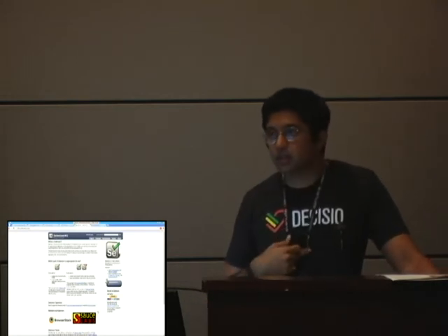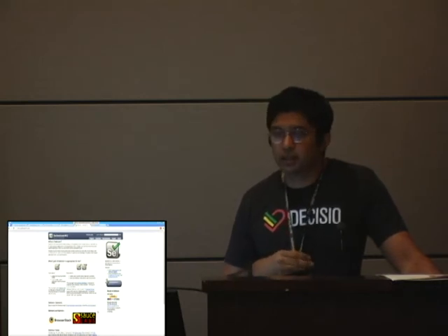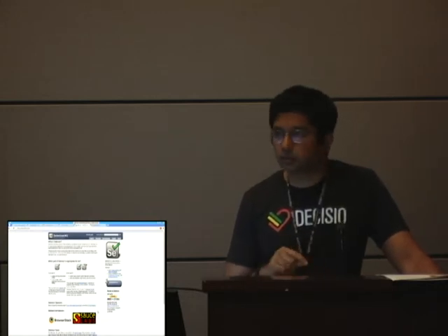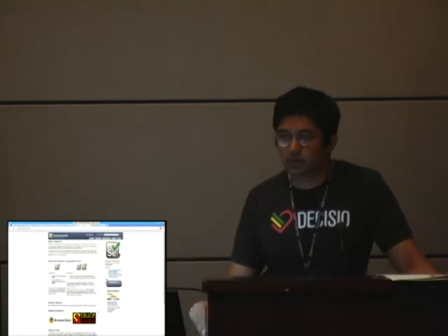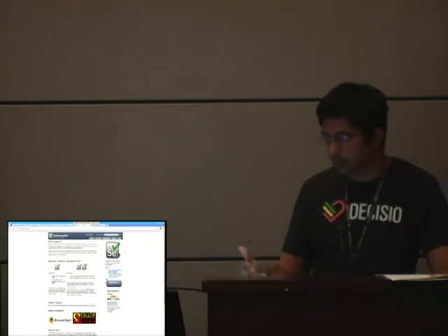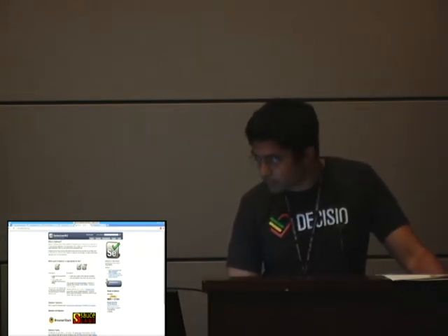When we went to the FDA, we initially said that we were only going to do WebKit-based browsers. The FDA didn't like that, so we went with just Chrome. Everything running on the bedside is either Chrome or Chromium, and we just have to test to make sure everything works in Safari, which we already know it does, but we have to document and test it. So that will be forthcoming.